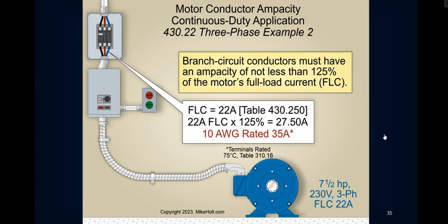Again, coming from the FLC, which if you flip over to those tables, I need an overhead camera here. I may actually get one. If you look at 430.248, that is single-phase alternating current motors. Table 430.249 is the FLC for two-phase alternating current motors. Not likely you're going to use anything out of that table. And then, here you go. Table 430.250, FLC for three-phase alternating current motors. That's where you want to go.